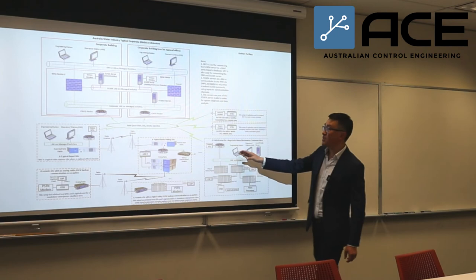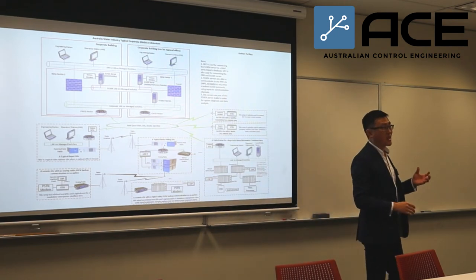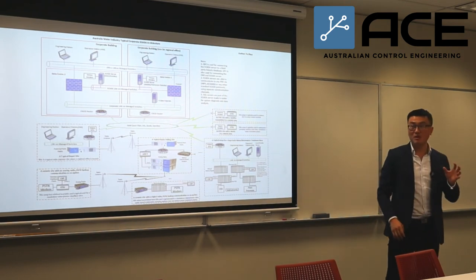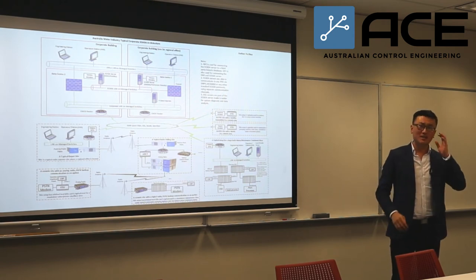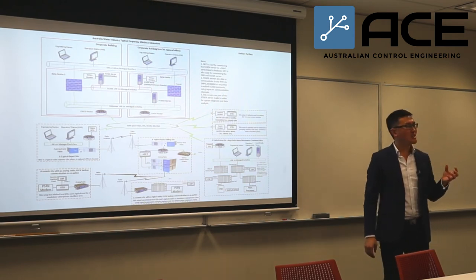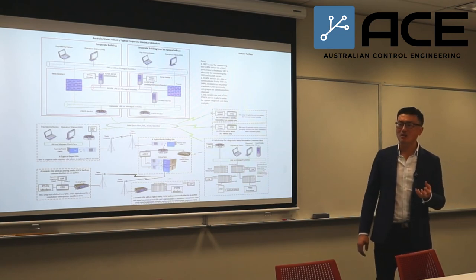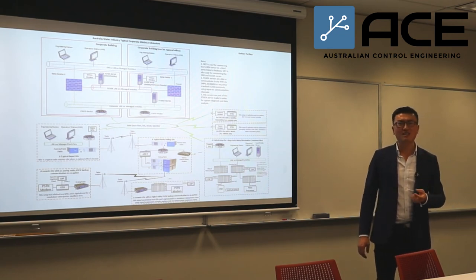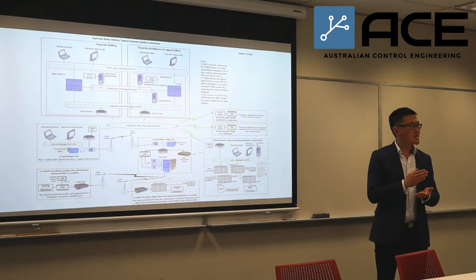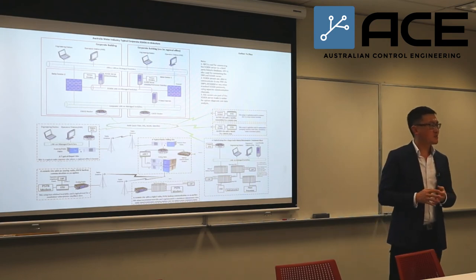In the extreme scenario, it can be 2,000 kilometers from the control center to the field. In that particular case, the timestamp event or class becomes extremely important. You need a DNP3 protocol — something like that — to guarantee the message is correct, was generated at a certain date and time, and to guarantee the traceability of the message as well.